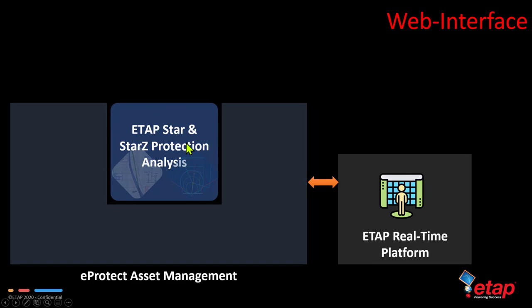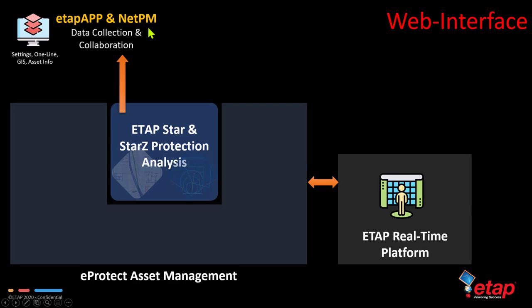We start off with ETAP that includes Star and Star Z protection analysis modules, the eProtect asset management system, and an optional connection to the ETAP real-time platform. The ETAP model, which is your existing single line diagram, can be augmented using ETAP App, and the data can be collected and collaborated on also using NetPM, or Network Project Management. That includes the settings, one-line diagram information, GIS information, and other asset information such as transformer impedances, grounding information, and other protection related data.